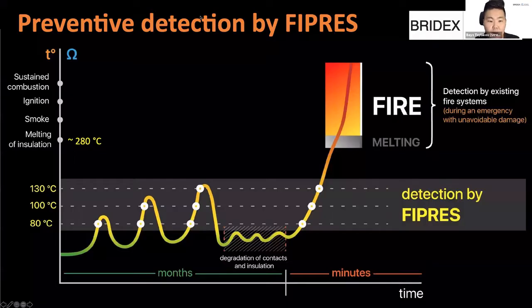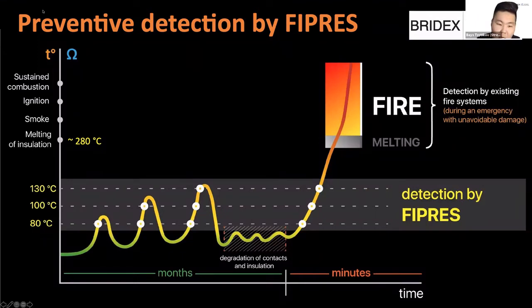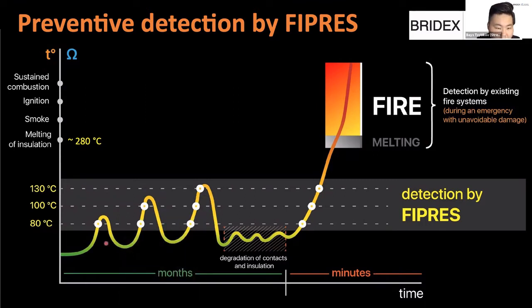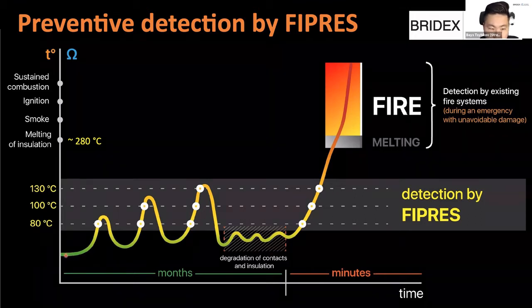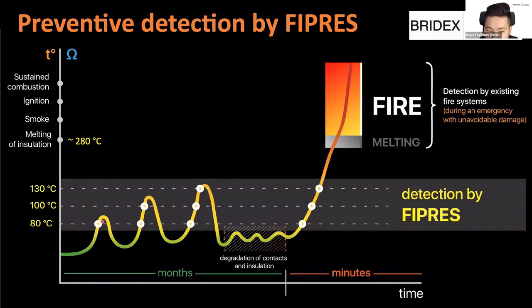Let's go further, and let's talk about the preventiveness of FIPRES. Here you can see the typical scenario of fire inside the electrical panel. This curve, let me use the laser pointer, is the temperature of the contact connection inside the electrical panel. Let's say the incoming cables connection. If you have a poor mechanically connected connection, it has a bigger resistance than a normal one. And with some high current, this contact starts to heat up.